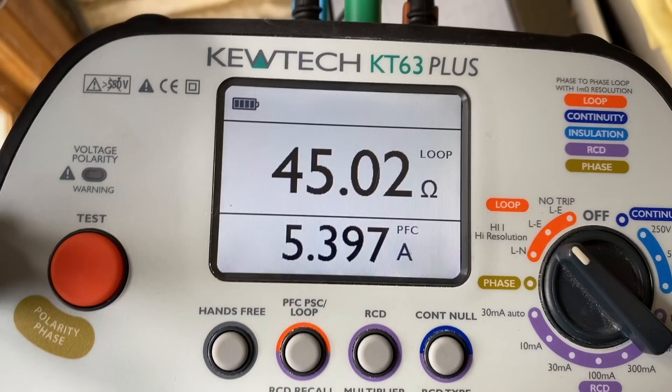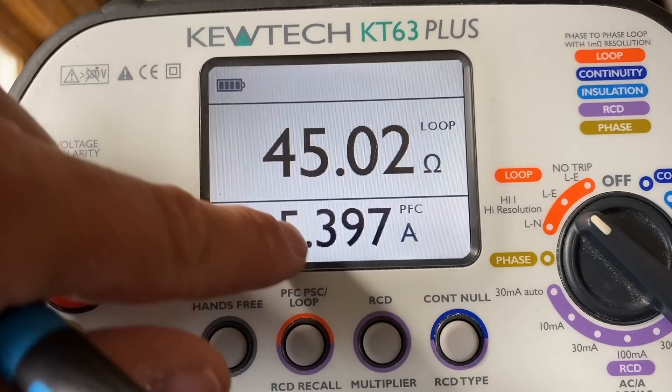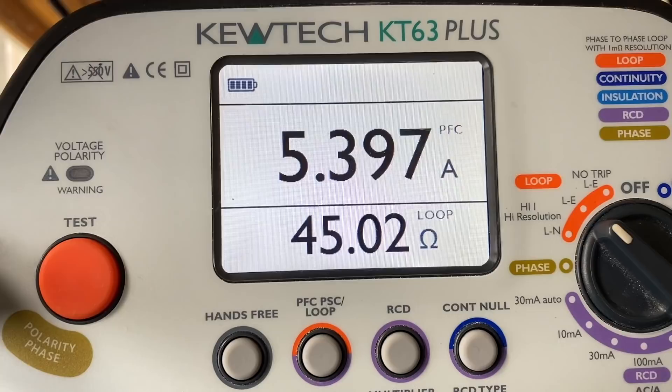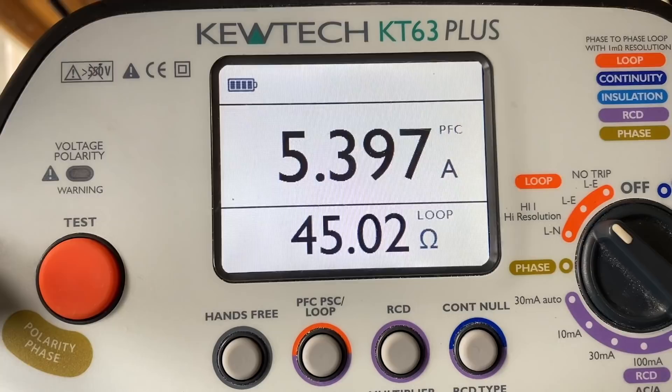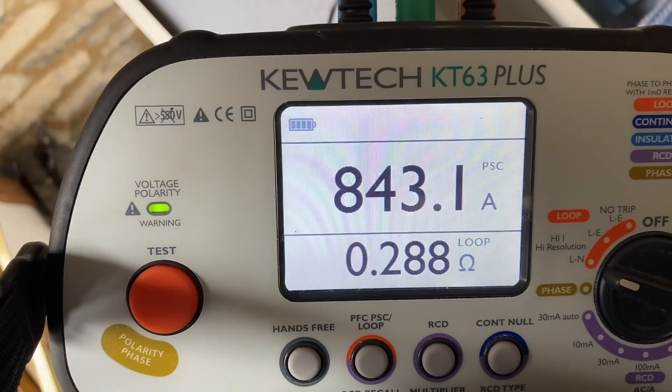I'm going to do my earth loop and PSC at the board now. Not bad — 45.02 ohms earth loop on that earth spike. Then 5.397 for the PFC. We'll just do a PSC now — disconnect and go between live and neutral. Should have got my head strap. Change the meter over. 843 amps PSC. Let's start recording the readings.